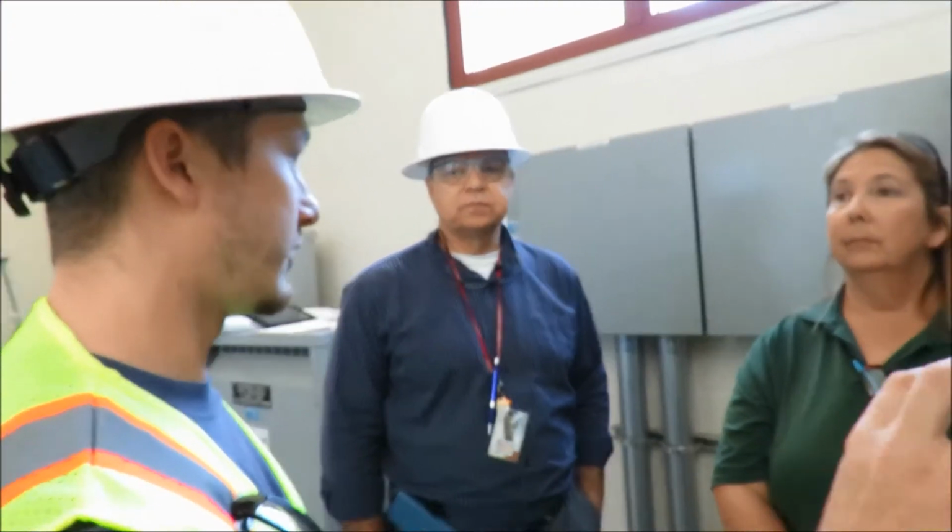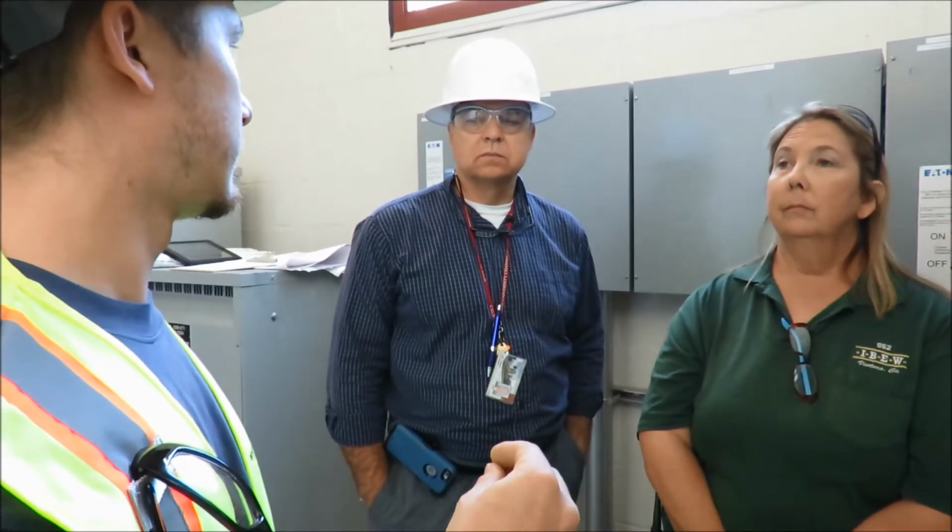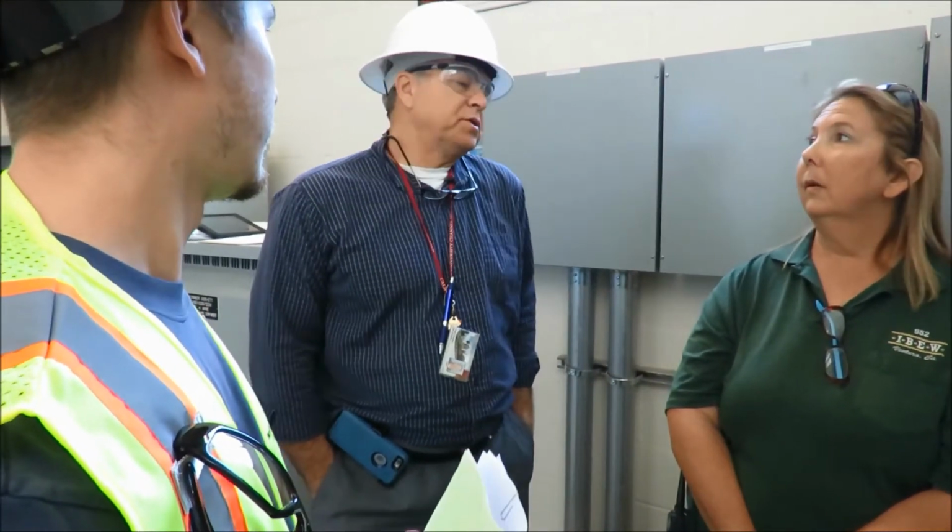It's a specialty. Essentially, there's a relay with normally open or normally closed contacts, depending on which one is needed for the door. On alarm, it either opens or closes, which allows the door to go down. That's all that we're doing. There's no power provided from our panel. So again, how the doors are going to operate is a big question mark.